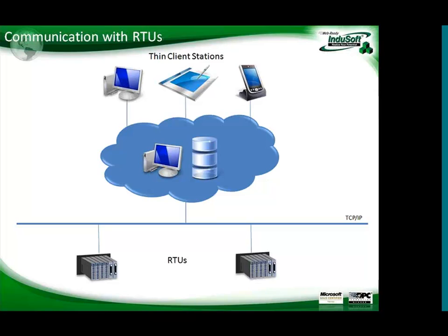And the third and last thin client solution supported by InduSoft is what we call SMA thin client. So from any device with a web browser, including the old cell phones, Nokia phones, any device with a web browser, you can type the URL for the server and visualize tag values in real time and visualize online alarms and even acknowledge the alarms. And all those solutions are linked to the built-in security system from InduSoft, so you can control the access to those screens, to this information, based on username and password.